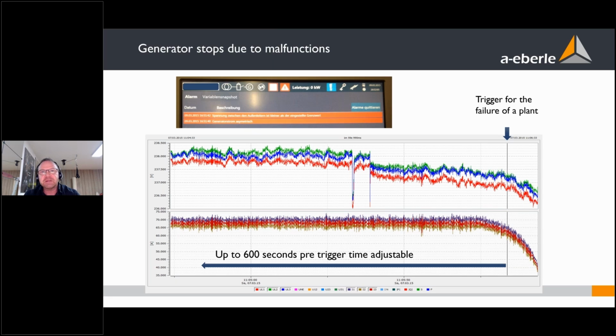Or in this case, I prove with my analyzer that the generator stopped, but the network has no problem. And if the network does not really have a problem, you often get no trigger from other analyzers.